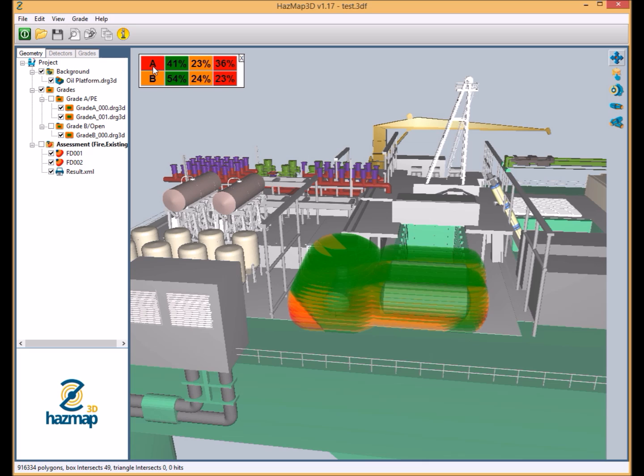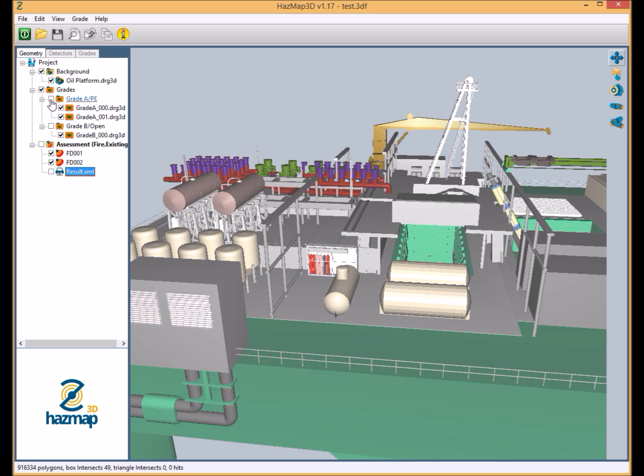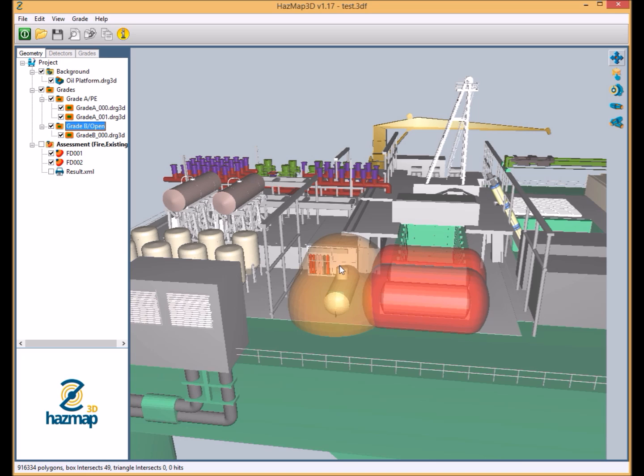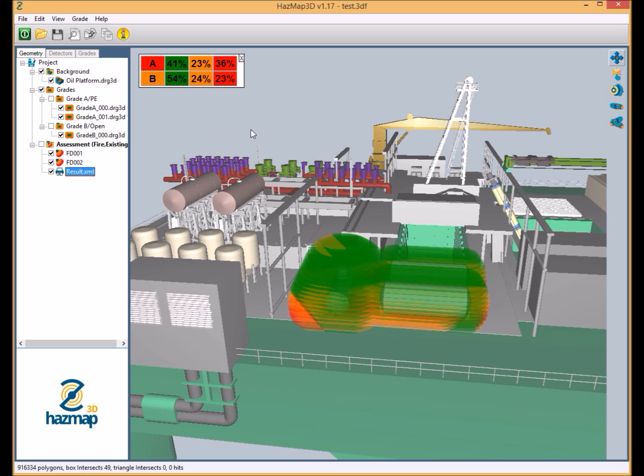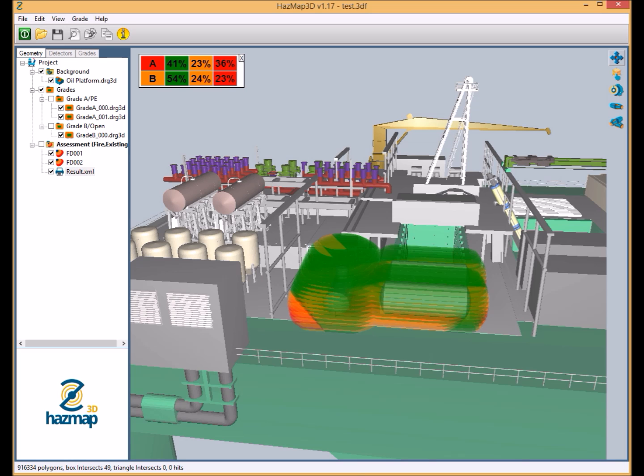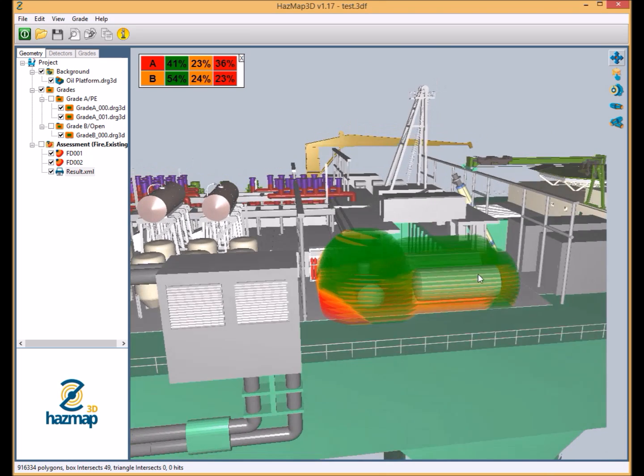The important thing to note is that we have, in the same assessment, a split of the grade A coverage and the grade B coverage. So if you remember before, we had two grade A pieces of equipment and one grade B piece of equipment. Now this is the same regardless of how many different grades you have within the scene. You will get split percentage coverages for each individual grade, and this is crucial when it comes to demonstrating compliance with most of the major engineering technical practices in the market today.